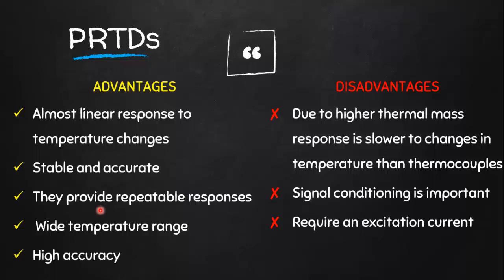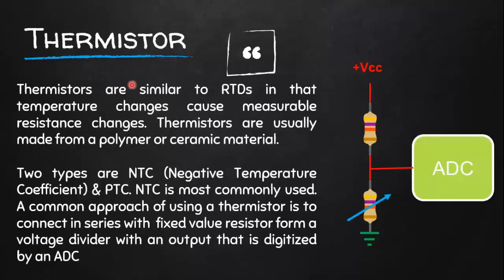RTDs can be used for a wide temperature range and are very accurate. The disadvantages include that due to their higher thermal mass, response is slower to temperature changes compared to thermocouples. Since they require excitation current, signal conditioning is very important in order to read the resistance.